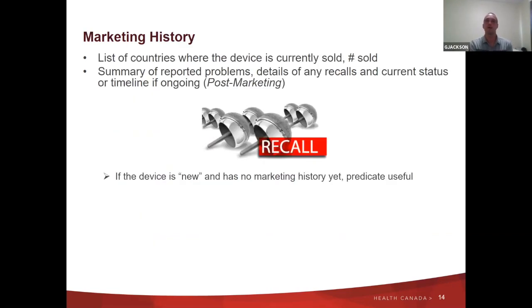Marketing history—we look at whether the device has been on the market elsewhere, say the US or Europe. We're interested in how many have sold, for how long they've been on the market, whether there have been any recalls or adverse events, and if so, what the manufacturer has done to correct or adjust for those. If the device is completely new, we may look at similar devices and say, these devices have had this kind of issue—how have you looked at managing this kind of issue?